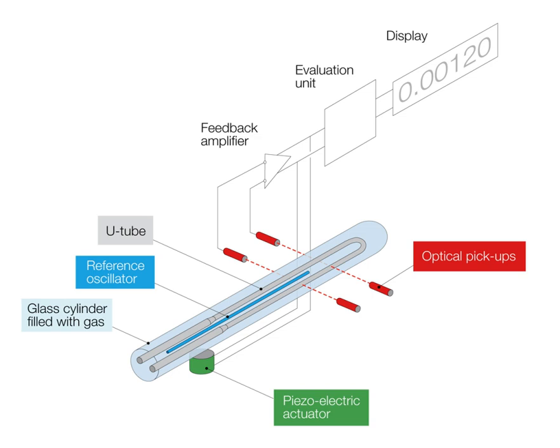a and b are the respective instrument constants of each oscillator. Their values are determined by calibrating with two substances of precisely known densities rho 1 and rho 2. Modern instruments calculate and store the constants a and b after the two calibration measurements, which are mostly performed with air and water.